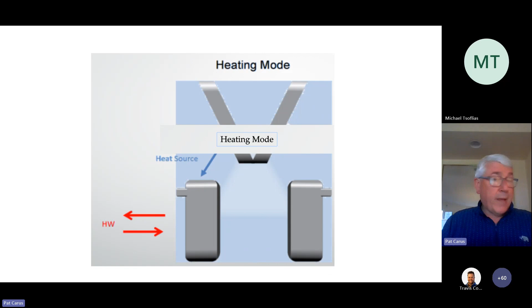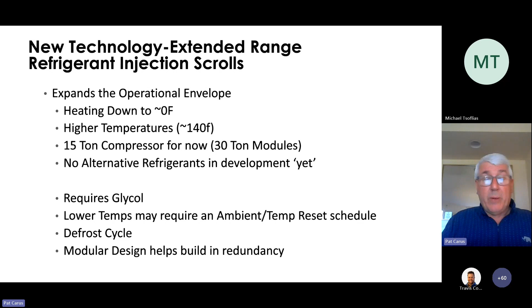Last big change for us is something called a refrigerant injection scroll. Typical scroll envelope has some limitations at cold temperatures, but we've got a technology that actually introduces refrigerant into the top cap, allows the envelope to expand a little bit, so we can heat all the way down to 0 and maybe a little bit farther. But the hot water that you would be able to produce as your ambient falls becomes less over time. It does require glycol. That doesn't seem to be a problem in many parts of the country, but California seems to have a little bit of issue with glycol.